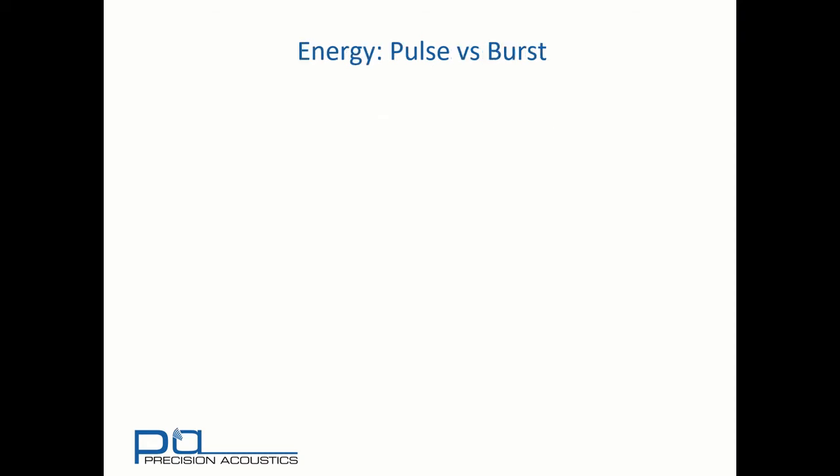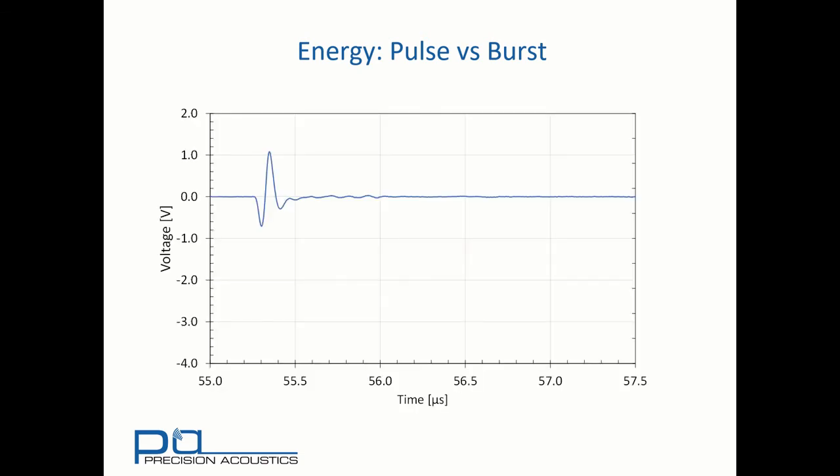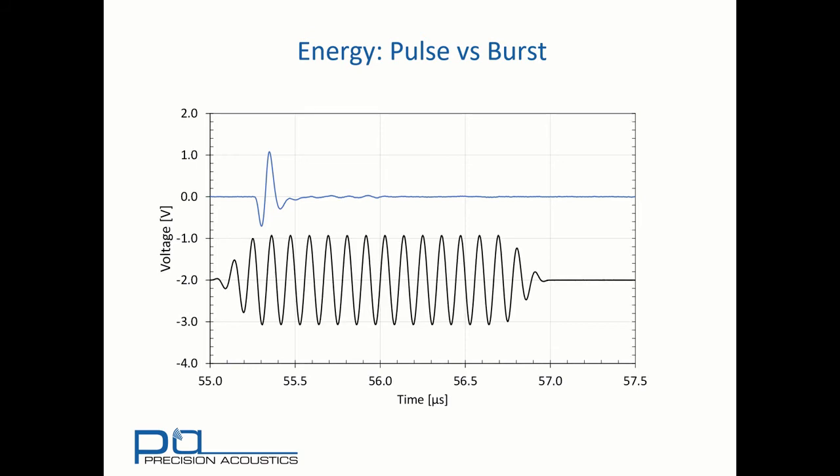So how might we get more energy into a sample of material that we're looking to measure? Again, considering our pulse signal that we saw previously, we'll contrast it with that of a tone burst of the same amplitude.